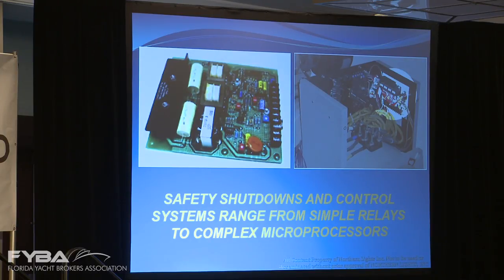So there's different ways to do it, but in the end, a generator has to protect itself from overheating, from low oil pressure, and there needs to be some way to detect a stoppage in the seawater flow that cools the wet exhaust. Now, different generator manufacturers do that different ways. Some detect seawater flow, and others actually measure the exhaust temperature at the wet elbow. That's the injection elbow, where the water cools the exhaust.